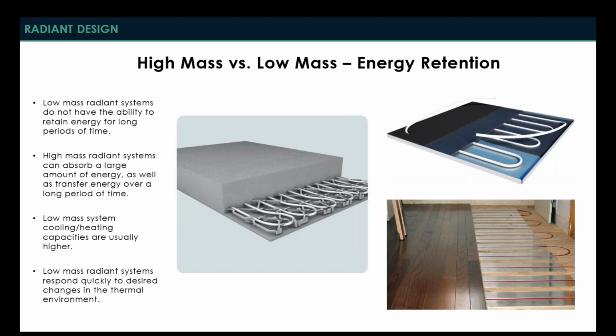Now, to the discussion of high mass versus low mass radiant systems, really it's all about energy retention. A low mass system does not really have the ability to retain its energy for a very long period of time. It essentially needs to be on and active in order to be doing its radiant heat transfer to occupants in the space. As soon as you shut the system off, in a very short period of time, that system will become the same temperature as the environment around it. High mass systems are very much different in that they can absorb a very large amount of energy. Think of a radiant floor system that has been placed into a concrete slab. That concrete slab can absorb this energy as well as transfer that energy back to the space over a very long period of time.